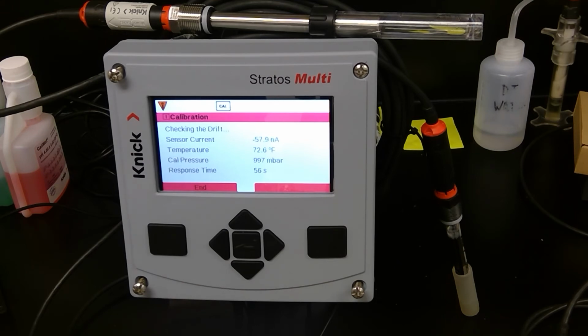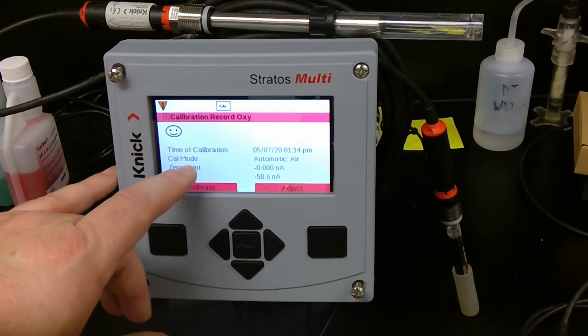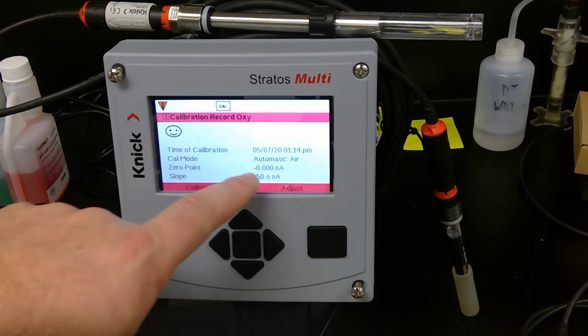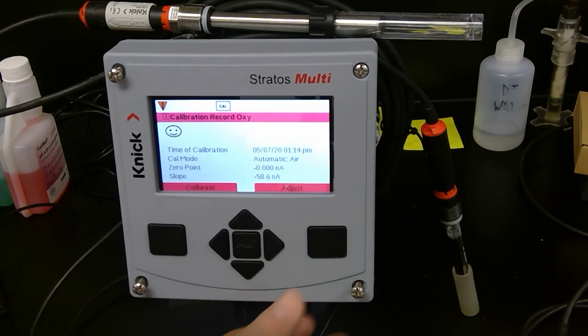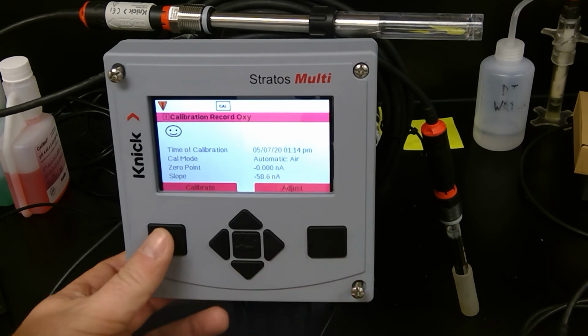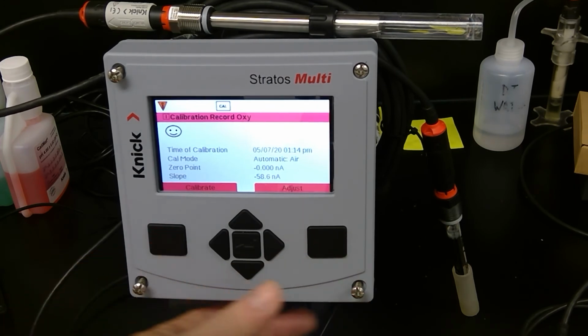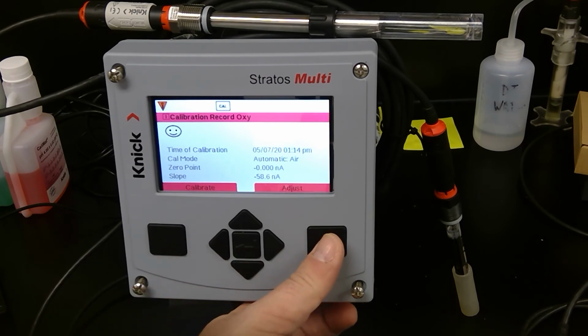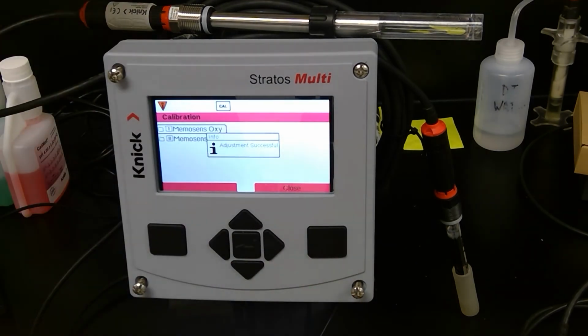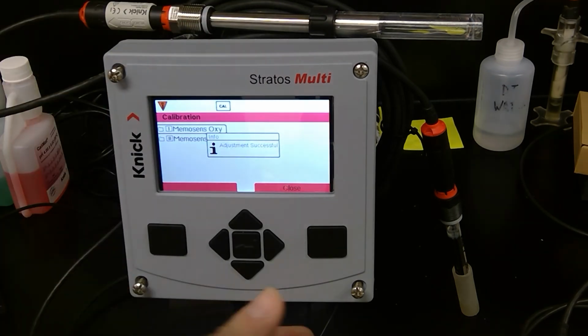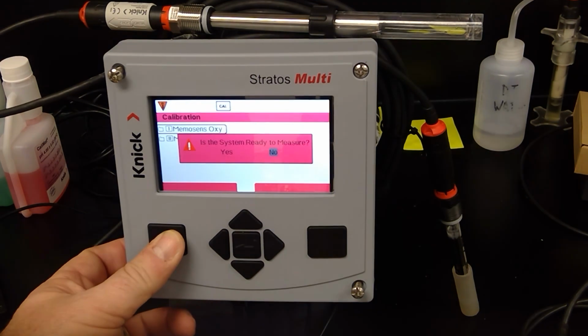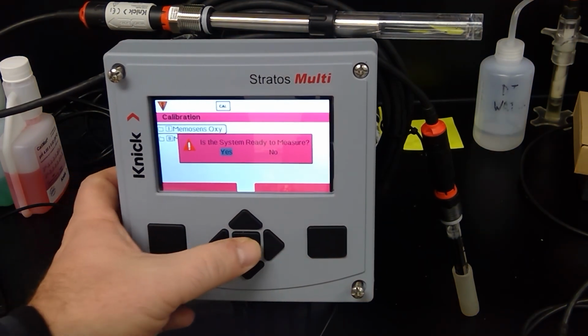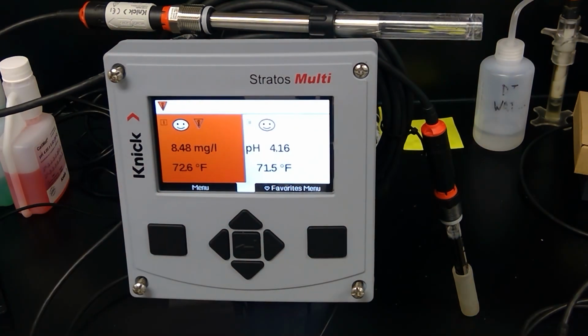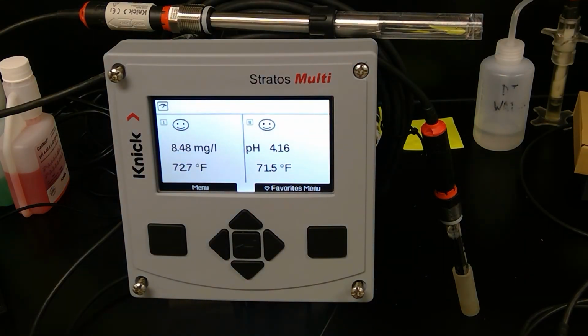replacement. So we've got about 3 seconds left and this is looking really good. We've got our smiley face, our cal mode was automatic in air, our zero point, our slope, date, and now I want to adjust. If I hit calibrate, it's going to put me back into calibration mode. Once you do the calibration, in this case we want to adjust. So now I'm putting that calibration adjustment into the electrode. I hit close and it asks me, is the system ready to measure? I'm just going to say yes, and then you'll see this clear from hold and it's back online.